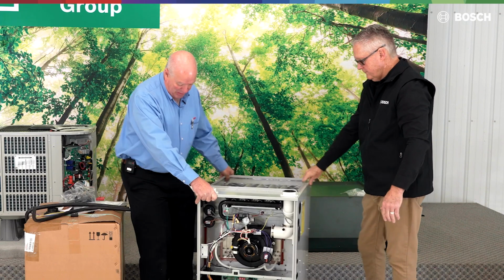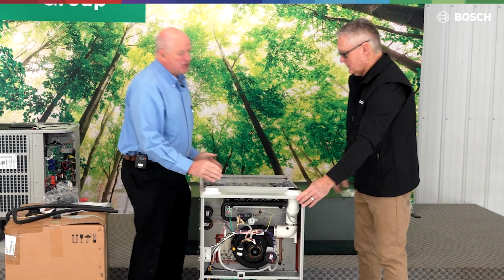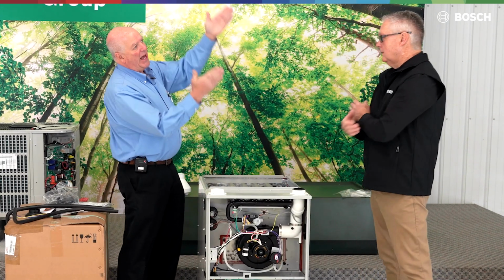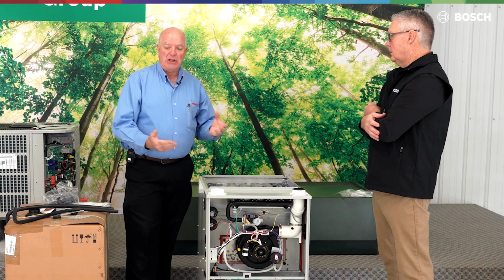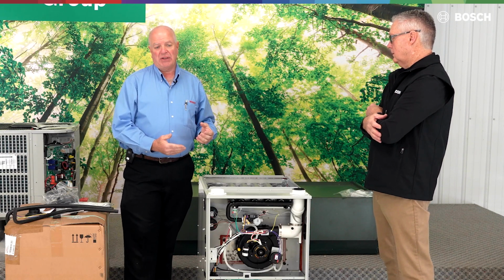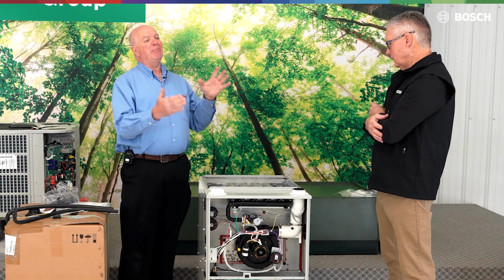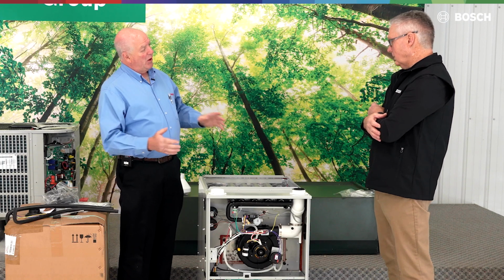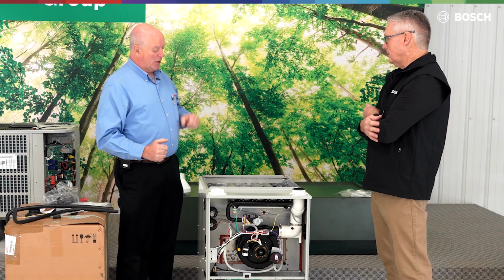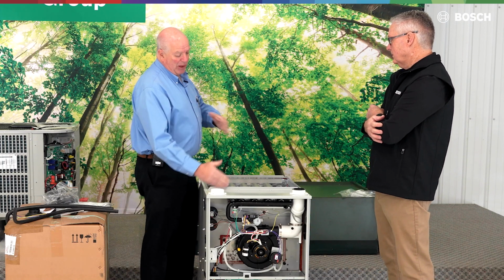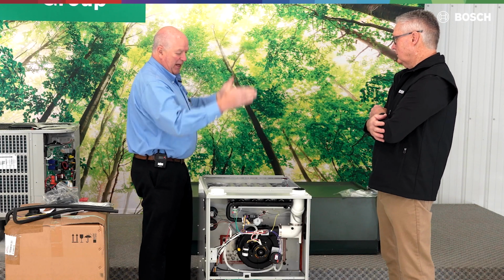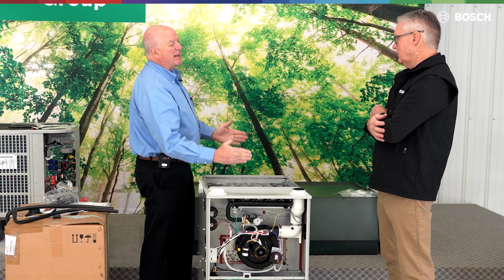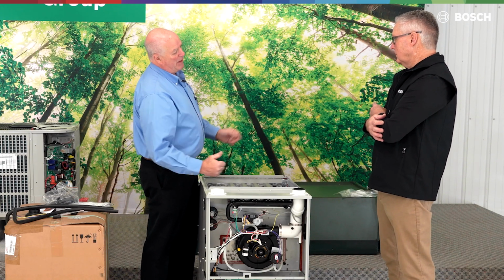Just ever so slight. Now what happens a lot of times, people have heartburn when we do that because our ductwork now is going to come off at an angle. With anything that we do with air, we should have canvas collars involved. Canvas collars are not for a misalignment, but for sound attenuation, so we don't carry that noise through the home or through the ductwork. Okay. So we can always favor that a little bit, bring our ductwork down straight, and let the canvas collar make up for that little bit of a goof up.